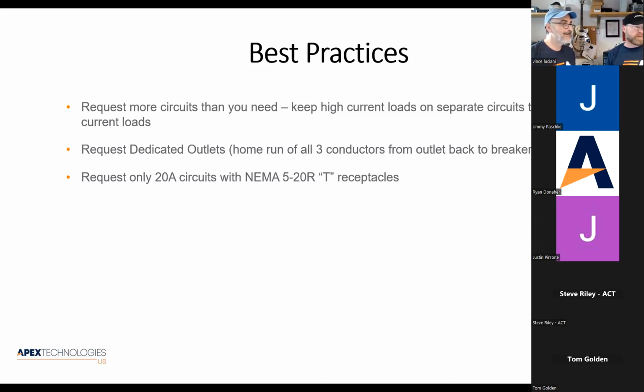So you had mentioned runs for all 3 conductors. Does that meet the requirements or definition of an isolated ground? So actually, very good. I mean, there are structures that have their own isolated ground. So the definition of isolated ground in the world of electrical is that, all right, a dedicated outlet is what we've already described. One outlet goes to one breaker and all 3 conductors are there. An isolated outlet really refers to commercial establishments where the conduit is metallic. Okay. And when you have metallic conduit, a lot of times, instead of Romex, where all 3 wires are in one jacket, you're using individual conductors.